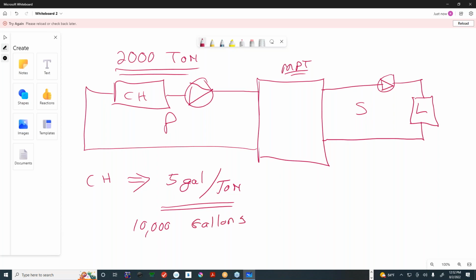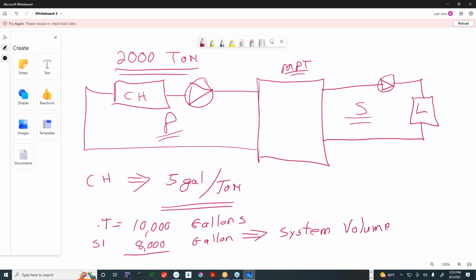And let's assume that between the primary circuit and the secondary circuit, the total volume of the system is somewhere, and I'm just arbitrarily making up a number, let's say it's 8,000 gallons. That's the system volume, so I'll put that in there, system volume, not including the multi-purpose tank. If I subtract the system volume, SV, from the total volume required by the manufacturer, the multi-purpose tank has to have a volume of 2,000 gallons. So that's how we figure out how big the multi-purpose tank needs to be.